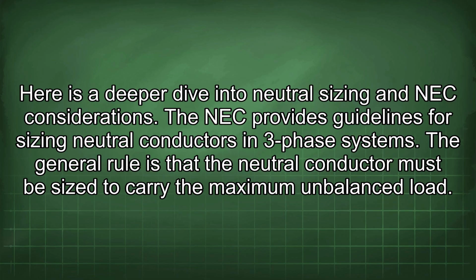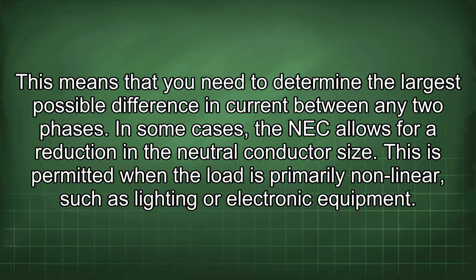Here is a deeper dive into neutral sizing and NEC considerations. The NEC provides guidelines for sizing neutral conductors in 3-phase systems. The general rule is that the neutral conductor must be sized to carry the maximum unbalanced load. This means that you need to determine the largest possible difference in current between any 2 phases. In some cases, the NEC allows for a reduction in the neutral conductor size.